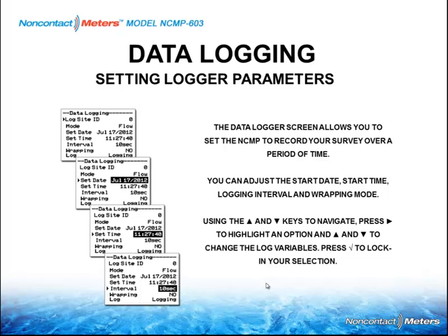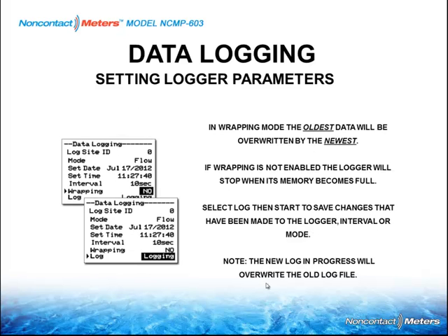So we select the sample interval, and you do have the ability, based upon how long you're going to leave it out there, for wrapping the data. If you wrap the data, after your 300,000 data points it can rewrite over the data, if you don't want to pick up the device and let it keep going in a loop. Most people will not wrap the device. Select logging, and the device will begin to log.